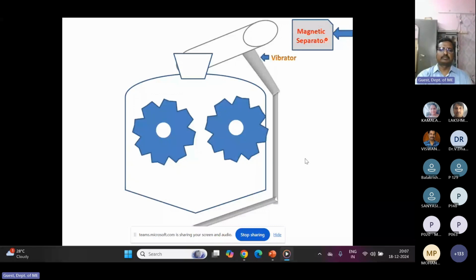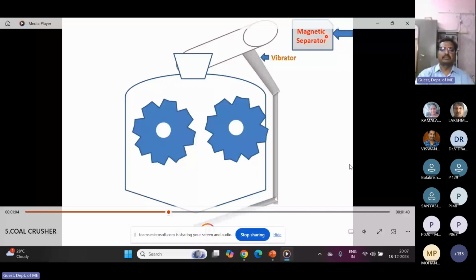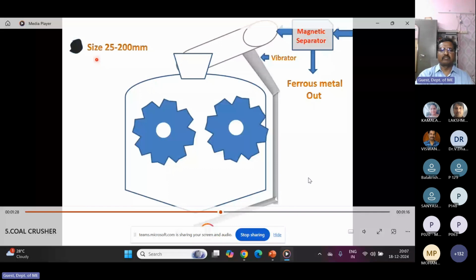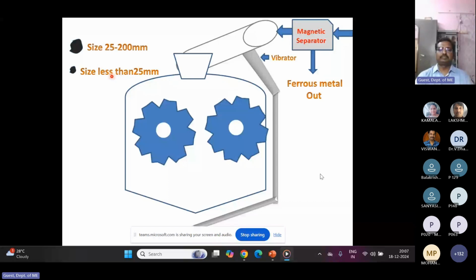There is a magnetic separator. When coal comes, the ferrous or iron particles are separated from the coal by the magnetic separator, and the ferrous metal is removed with its help, so that our crusher will not be harmed by the ferrous or iron metal. Then the coal will go to the pan. The coal size will be 25 mm to 200 mm, and we want the crushed coal size to be less than 25 mm. When the coal is crushed, its size will be less than 25 mm.